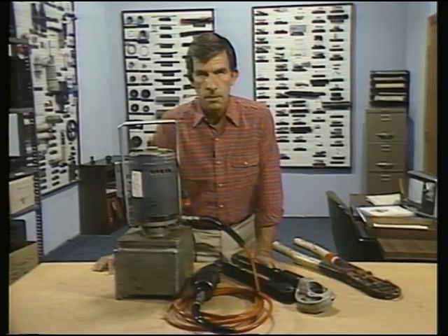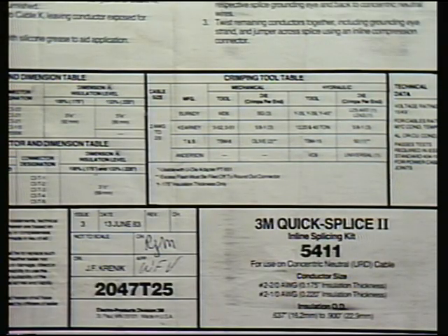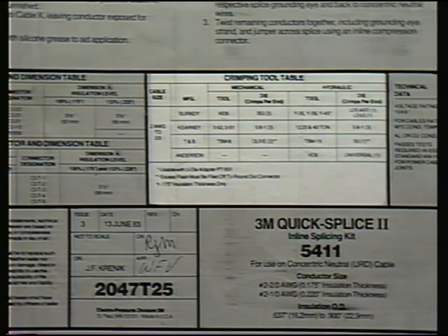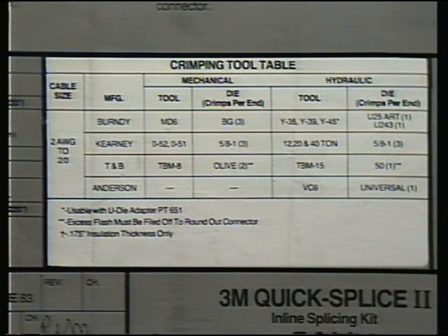connector applications. Most presses have sizing inserts called dies that allow the press to be used on different size connectors within a certain range. You must be sure you're using the correct press and die for the connector you'll be working with. This sizing information can generally be found on the connector itself, or it may be written into the manufacturer's instructions. Connector instructions generally come separately from any other splicing instructions. With the correct equipment and the instructions close at hand, you're ready to begin the splice.